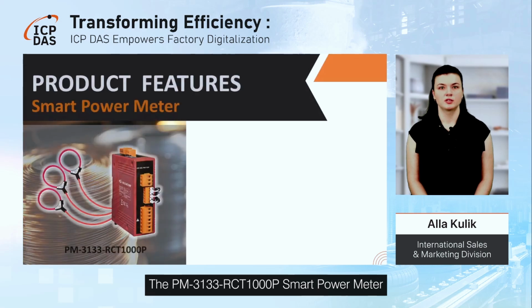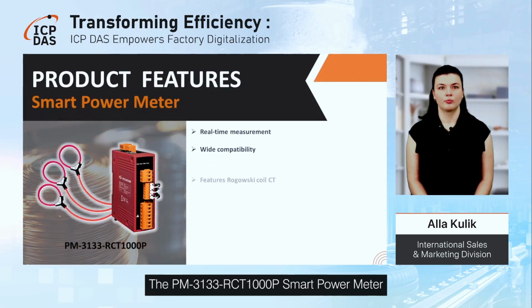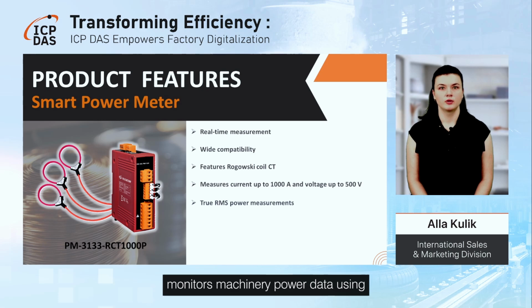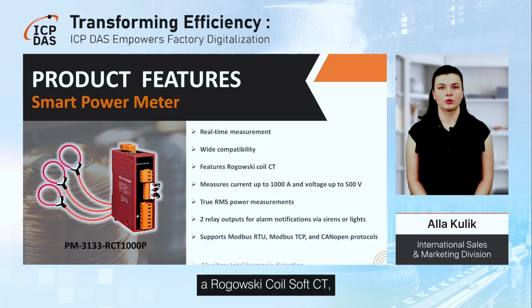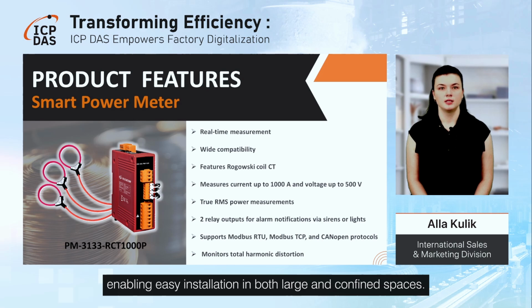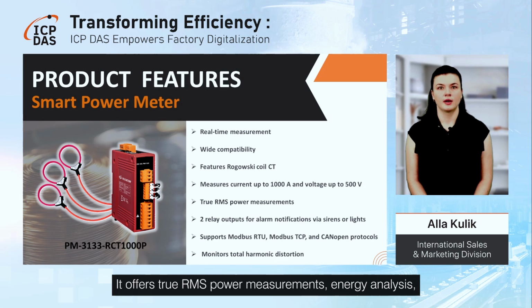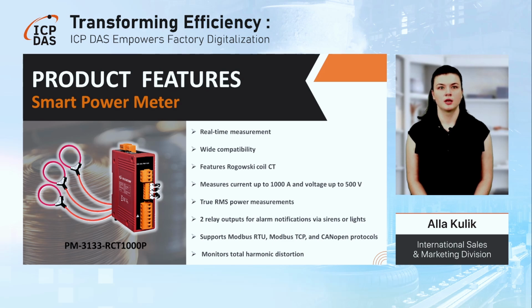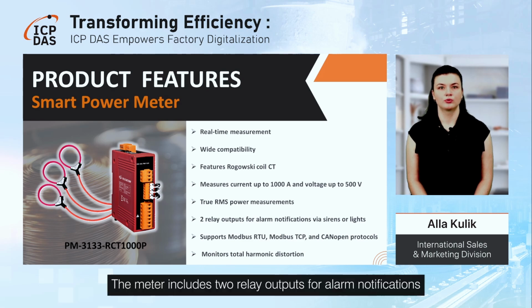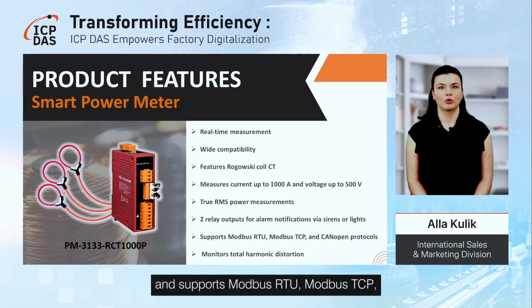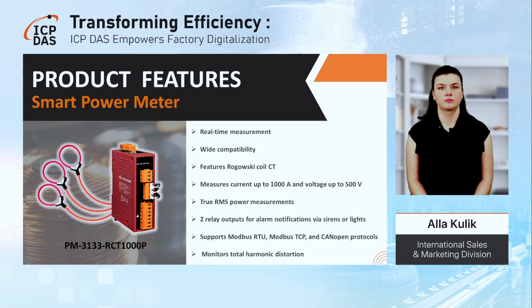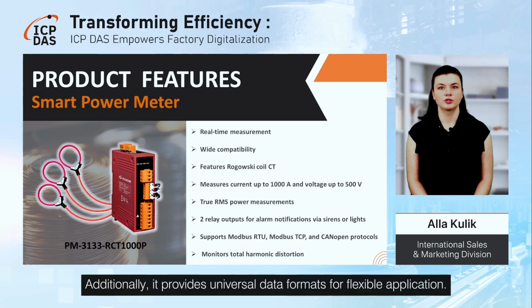The PM3133 RCT1000P smart power meter monitors machinery power data using a Rogowski coil soft CT, enabling easy installation in both large and confined spaces. It offers true RMS power measurements, energy analysis, and total harmonic distortion monitoring. The meter includes two relay outputs for alarm notifications and supports Modbus RTU, Modbus TCP, and CANopen protocols for seamless integration. Additionally, it provides universal data formats for flexible application.